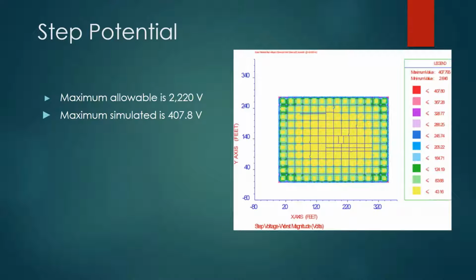Our grounding grid was simulated by our sponsor, Burns McDonnell, in a program called CDEGS. We were not able to simulate this ourselves, as a single key of CDEGS costs $20,000, but our sponsor still wanted us to get the experience of seeing what a simulated grounding grid looks like. So the picture we're looking at is the step potential for our grounding grid. The maximum allowable step potential is 2,220 volts. Our grounding grid, at a worst case, hit 407.8 volts. This was only around the edges of the substation, the corners.